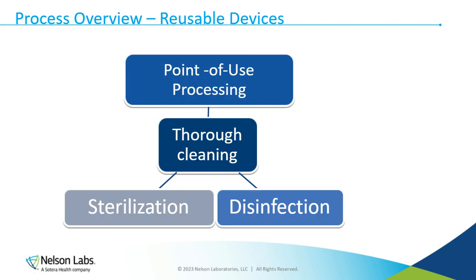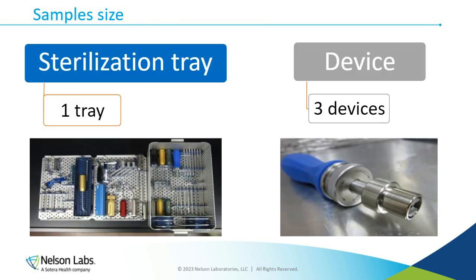Sterilization is just one part of the reusable medical device process, where we go through cleaning, disinfection, and then sterilization — and sterilization is a very important part of that process. When we go through a steam sterilization validation, one of the first things we need to think about are the sample sizes we're going to use. Generally, we'll ask for one completely populated tray if we're validating a sterilization set, or a minimum of three devices if we're validating an individual device.